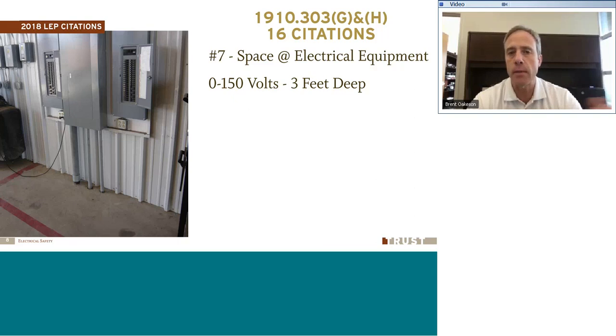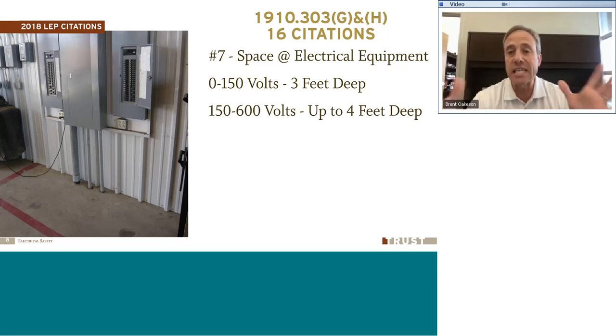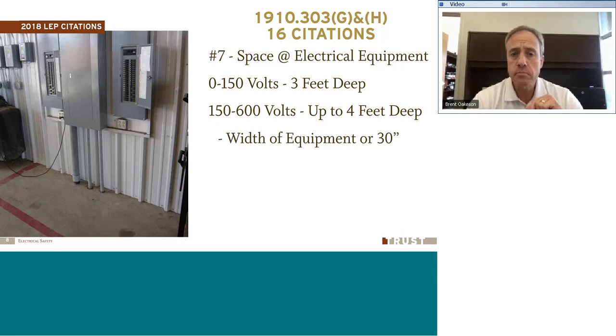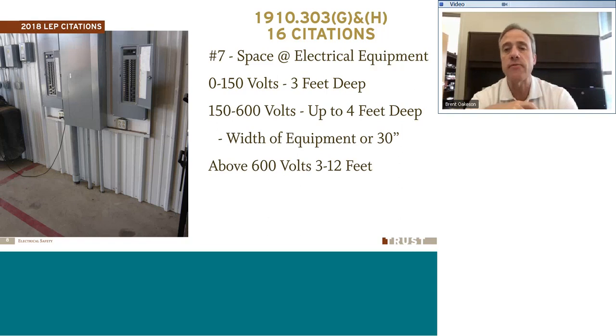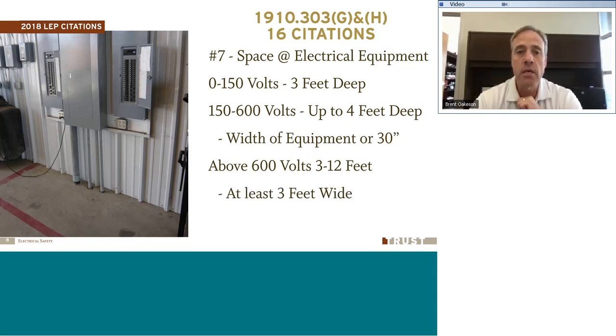So up to 150 volts in that panel, that space needs to be 3 feet deep. Depending on the conditions, in other words, the design and condition of the panel itself, it may need to be up to 4 feet deep, depending on the voltage and the configuration of that particular panel. If it's a high voltage panel, if it's over 600 volts, then again, depending on the configuration of this panel, that space could be anywhere from 3 to as much as 12 feet. And so, if you've got high voltage panels, then we would need to take a close look at the specific design of that panel and what the configuration is to determine how deep that space is that needs to be maintained free and clear in front of that piece of equipment. Again, at least 3 feet wide, and could be wider depending on the equipment.